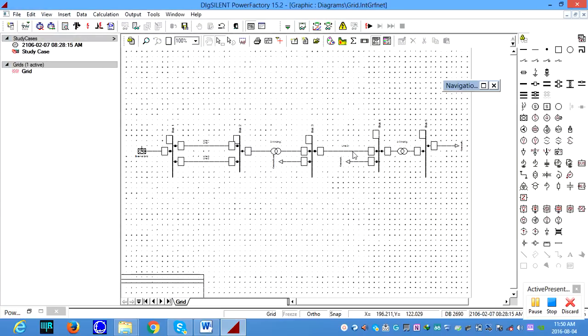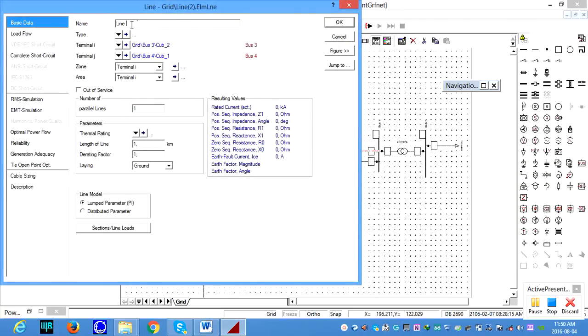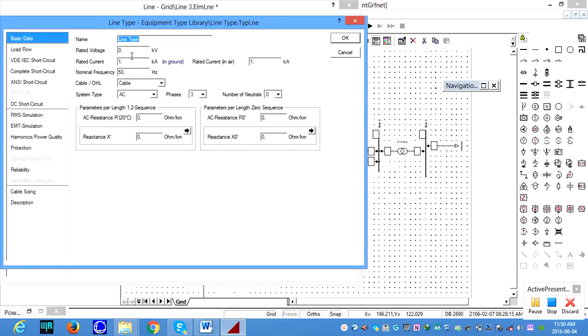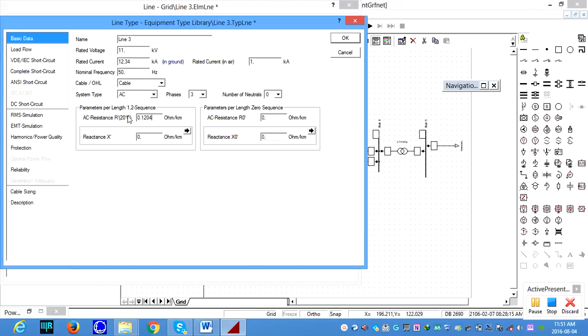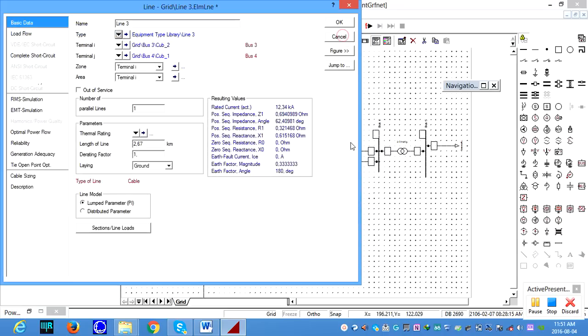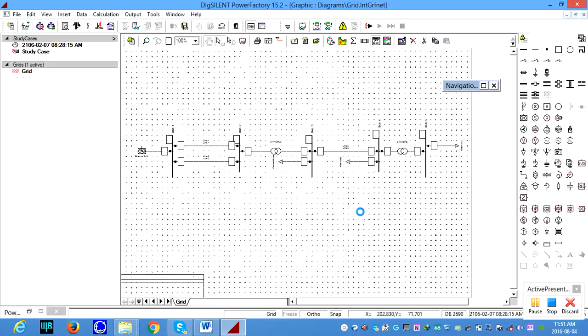Okay, next we're leading to the last line, line 3. Change to line 3, and the line length 2.67 kilometers, and the type, you can go into line type, new, let's say line 3. And the rated voltage is 11 kV, and the rated current we can say 12.34 kiloamps, and the resistance and reactance. The resistance is 0.1204 ohm per kilometer. The reactance is 0.2304 ohm per kilometer. Okay, we are happy about the line parameters.